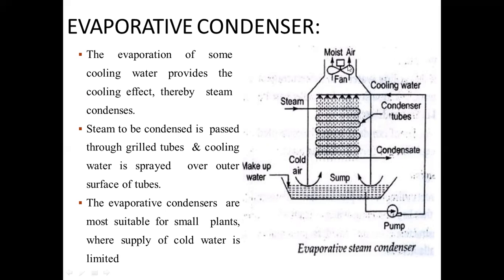There are eliminators which stop the loss of water. Only air is allowed through, while the water droplets settle down at the sump, and can be reused again and again. A few water particles leave the system with the air, so makeup water is used to compensate for that water. The evaporation of some cooling water provides the cooling effect, thereby steam condenses. Steam to be condensed is passed through a grilled tube, and cooling water is sprayed over the outer surface of the tubes. The evaporative condensers are most suitable for small plants where supply of cold water is limited.